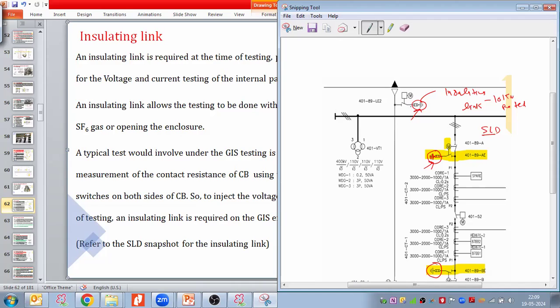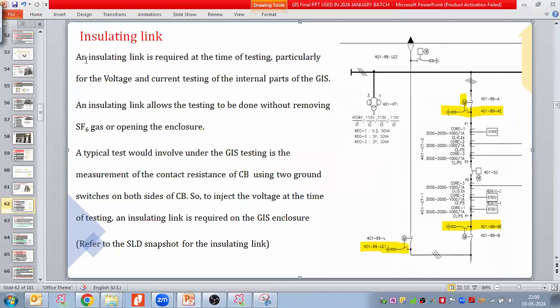Do not represent direct grounded earthing switch. In the grounding, there must be an insulating link. This is important for the testing purpose. So this is the insulating link that needs to be indicated in the single line diagram. Why are we taking that insulating link? So what are these three lines also? RYB phase. Oh, okay. Yeah.